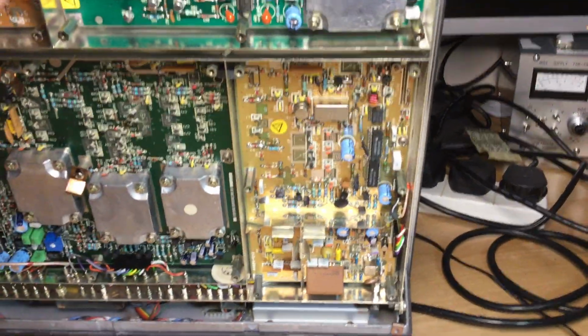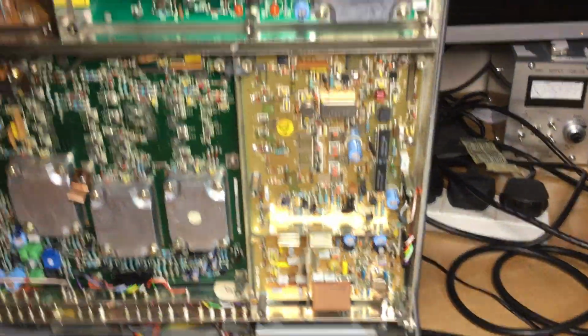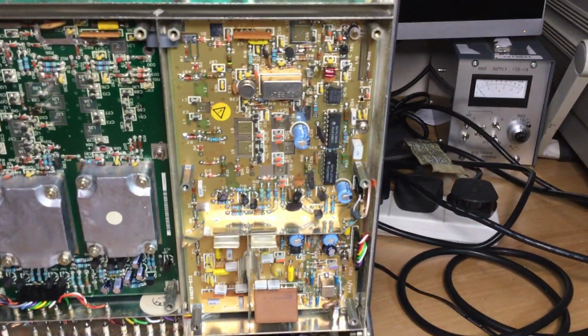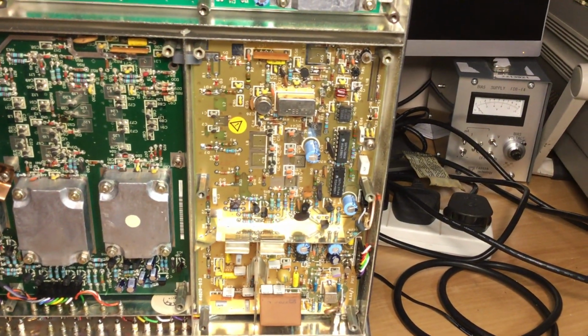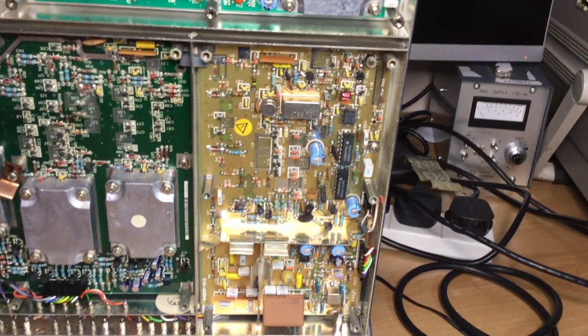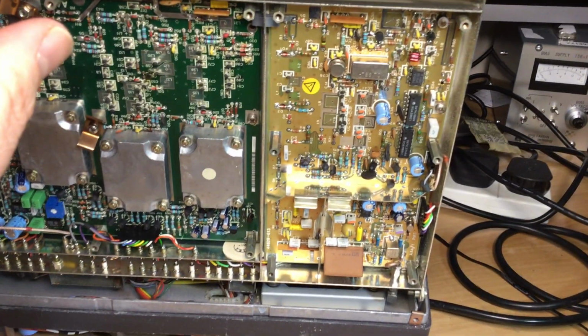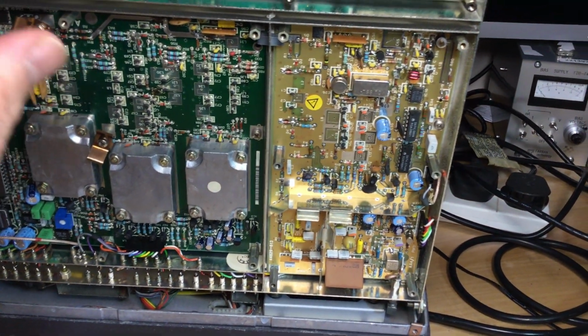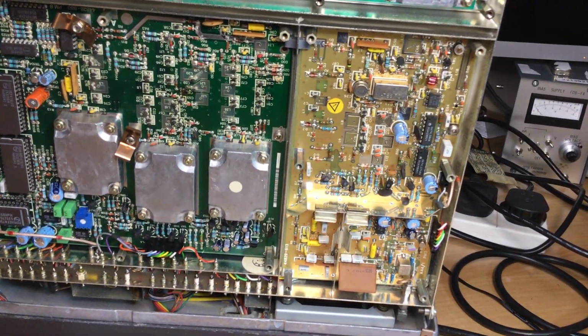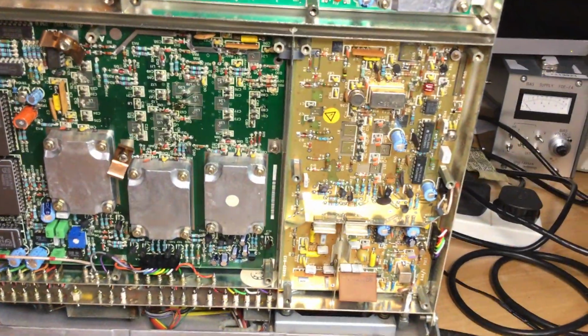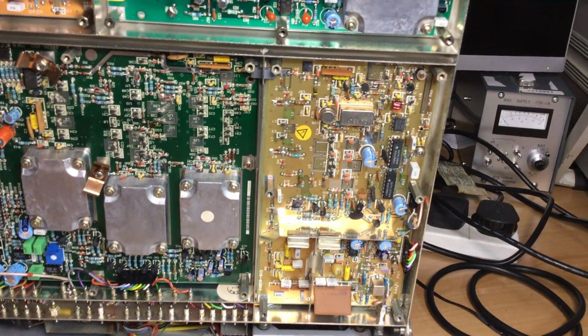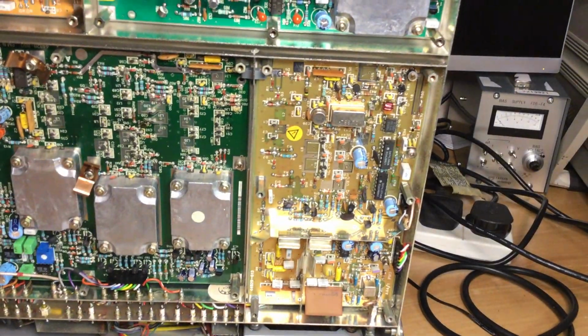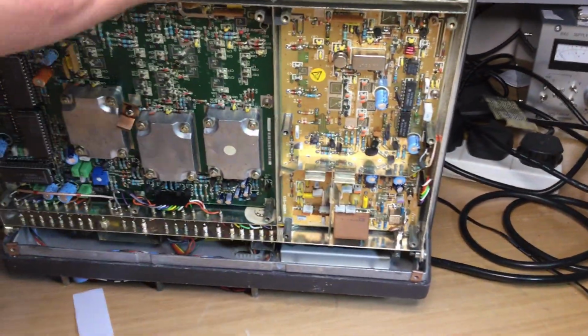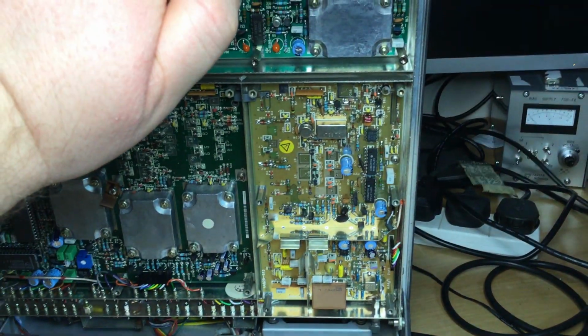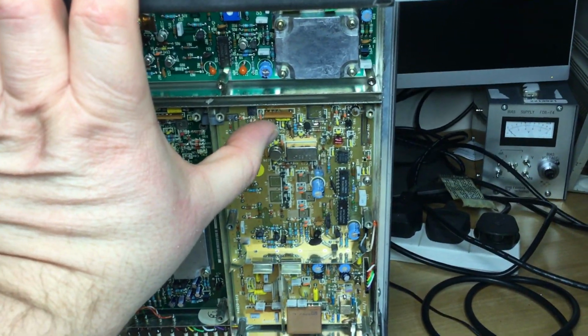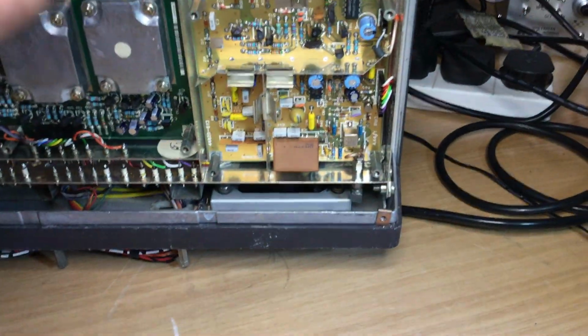We've got this board down here, and this particular board, if I'm not mistaken, is AA4. That's AA4. So that's the low frequency synthesizer and output amp, it says in the manual. And basically what that is, the RF section for the signal generator, the RF output, and it uses these thick film OM modules which were made by Mullard, like that one down there in the bottom.